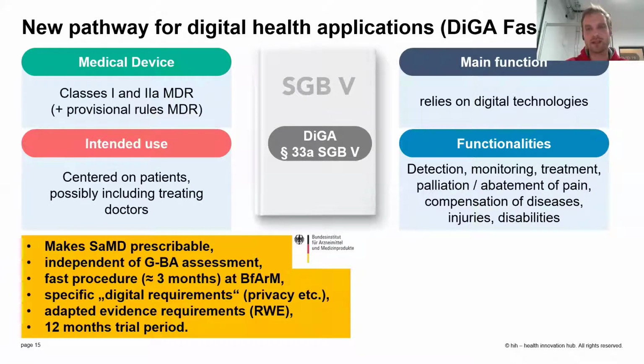You might remember that class 1 is probably not very feasible anymore for software under the new MDR regime, but the provisional rules of the MDR, which allow you to enter the market following the requirements of the MDD, are also applying here. So a medical device class 1 or 2A under the MDD is at the moment also allowed to apply for this DiGA Fast Track.